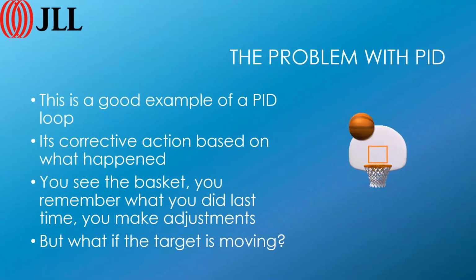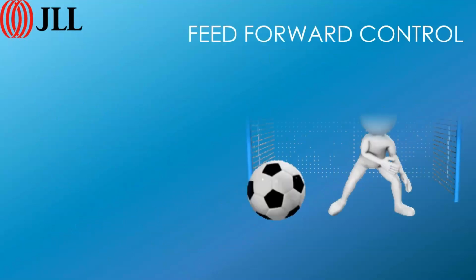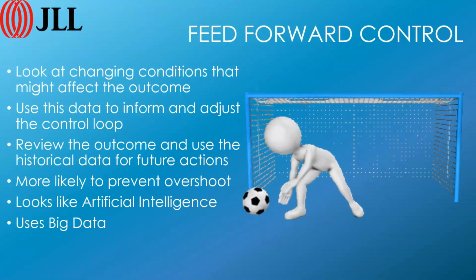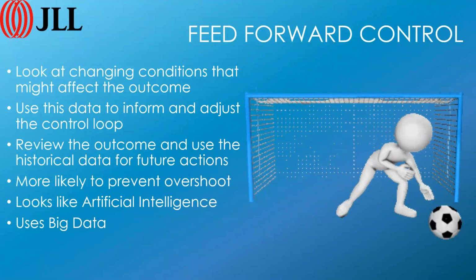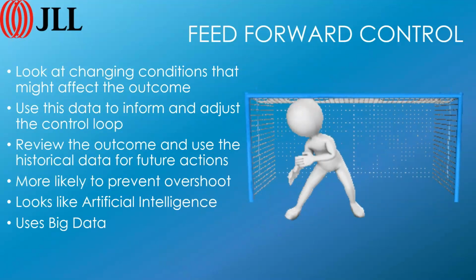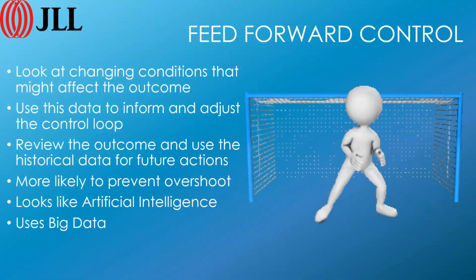If you look at that basketball player, he's shooting at a hoop, and it's going through all the time. But once in a while, he'll clank it, he'll hit the rim or something like that, and he'll think a little bit about what he was doing and realize that he's got to hold his hand differently, or he's got to make some adjustments to it. And so that is an adjustment after the condition occurred. That is typically what you see with PID. But what happens if you have changing conditions and you're trying to meet those changing conditions? So we want to use something called feed-forward control.